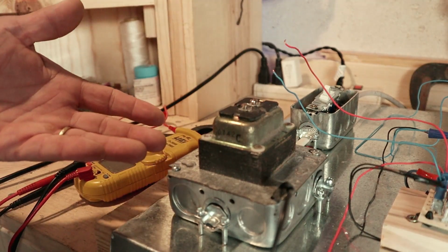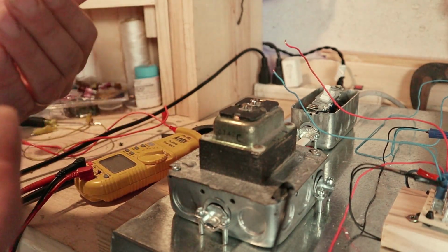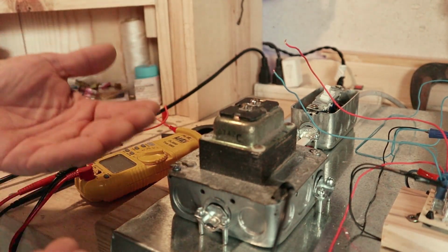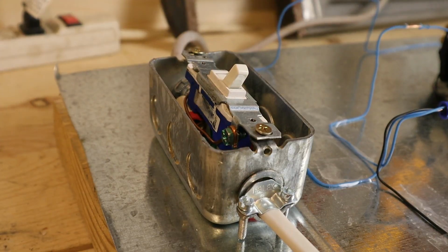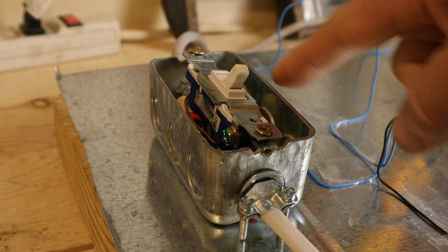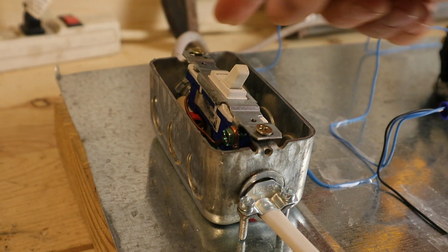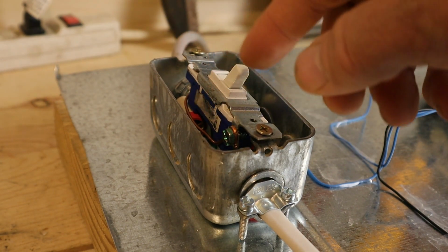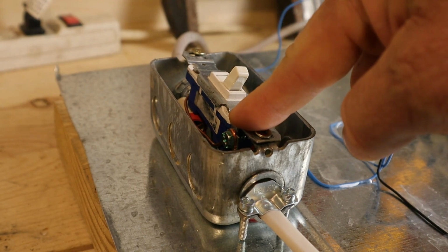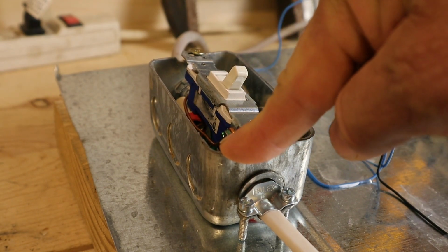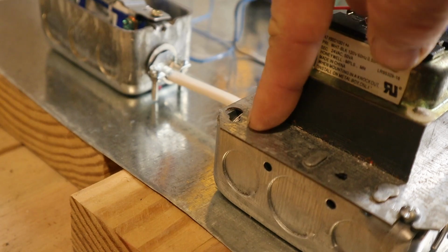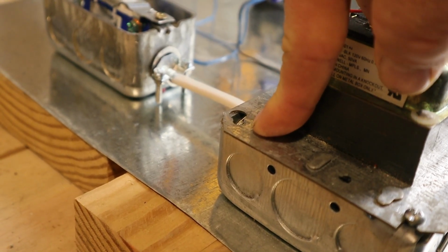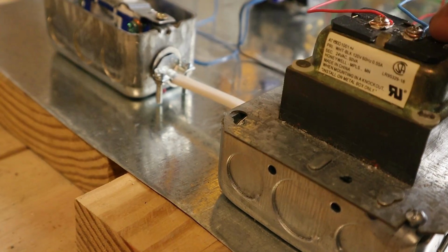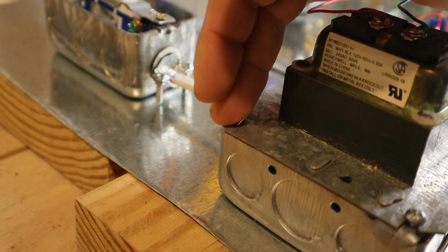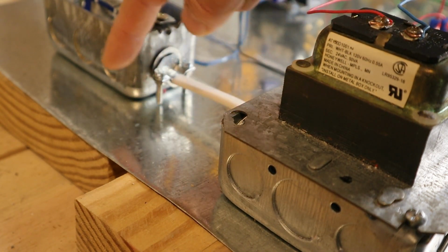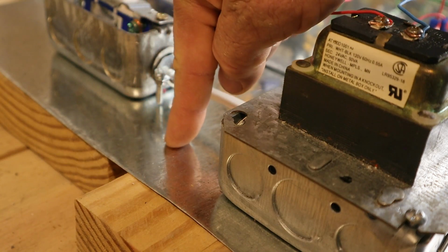So what is a floating circuit? Why is that important to know? And how can this help us quickly diagnose where a short might be located? Your entire low voltage control circuit starts with the high voltage coming into your unit, and with that voltage is going to be a ground wire. That ground wire is going to connect to the switch itself and to any metal boxes. That ground wire will continue on and connect to any other metal boxes that might be along that circuit, and any other metal touching these boxes is also going to be grounded. So the sheet metal that these boxes are mounted on will also be grounded.